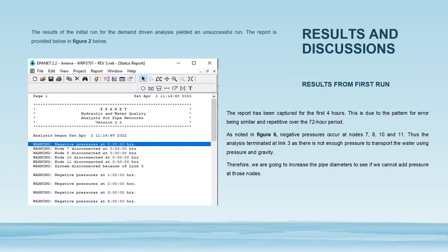We are now going to discuss the results obtained from running the EPANET software. The report has been captured for the first four hours, as the pattern for error is similar and repetitive over the 72-hour period. As you can see on figure two, negative pressures occur at nodes 7, 8, 10, and 11. The analysis terminated at link three as there is not enough pressure to transport the water using pressure and gravity. Therefore, we are going to increase the pipe diameters to add pressure at those nodes.